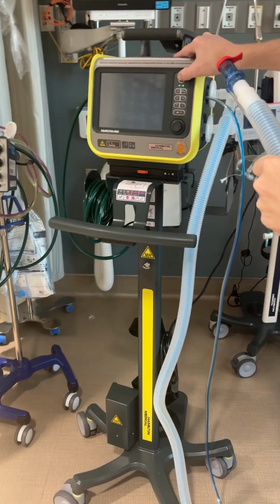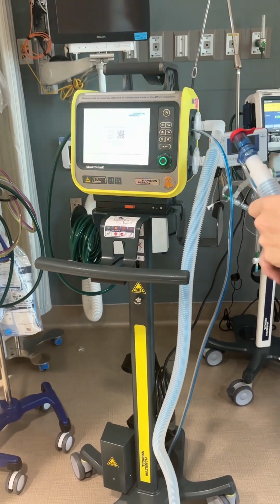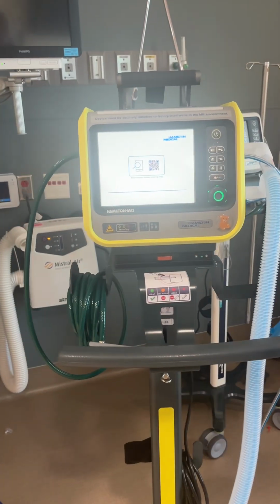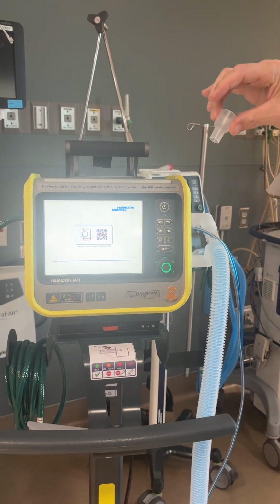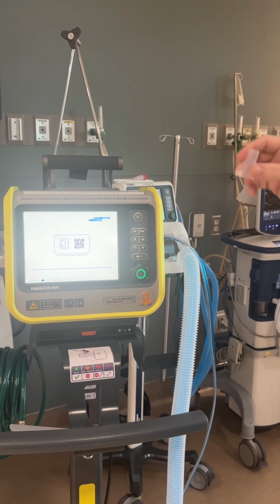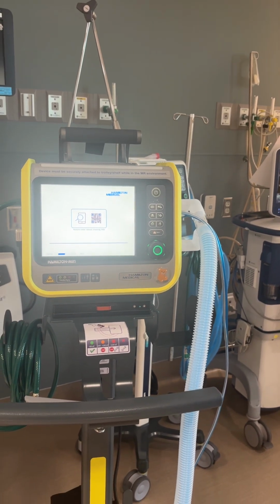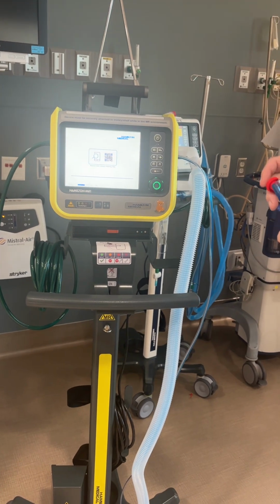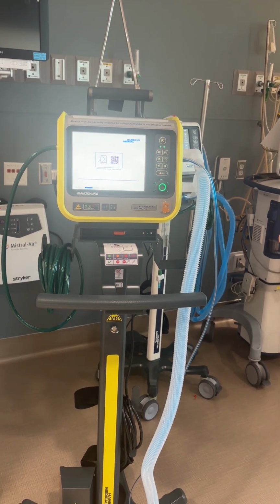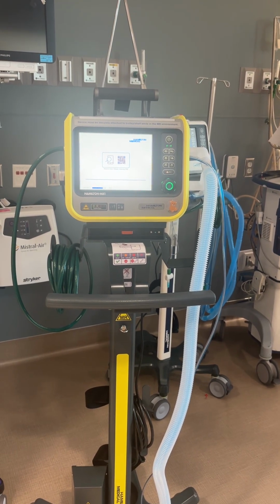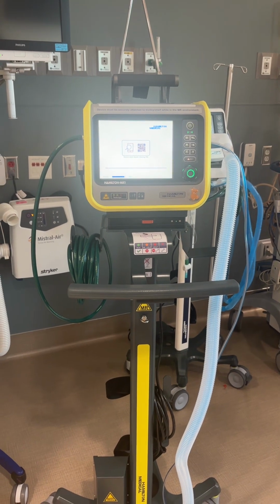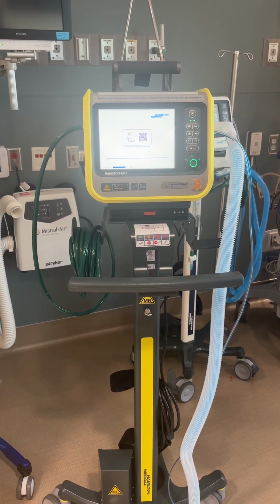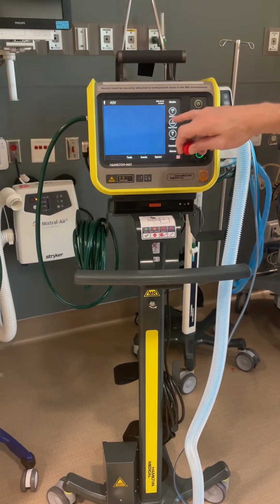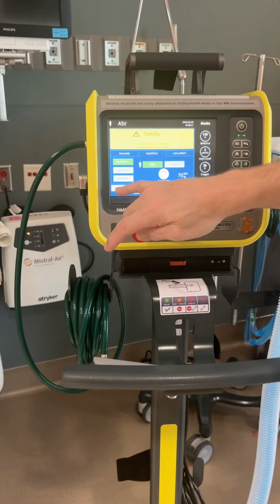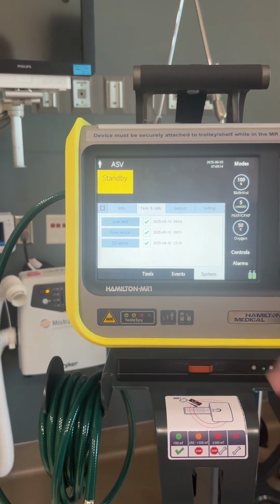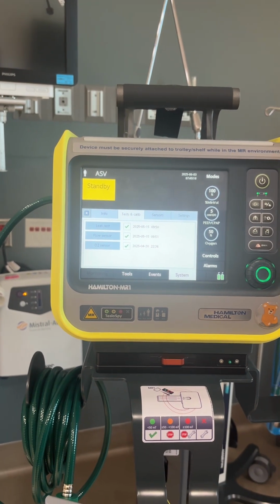Then you're going to turn this on for the vent, and it's going to prompt you to go through the leak test. This is your little valve, your little adapter, to do your leak test on your expiratory valve. So your flow sensor. It takes a little time to set up. Any kind of stuff you need, there's a QR code right there. So you want to do your pre-op check, and you can see it's being done. But you want to do this before you take a patient down, even if it looks like it's being done.